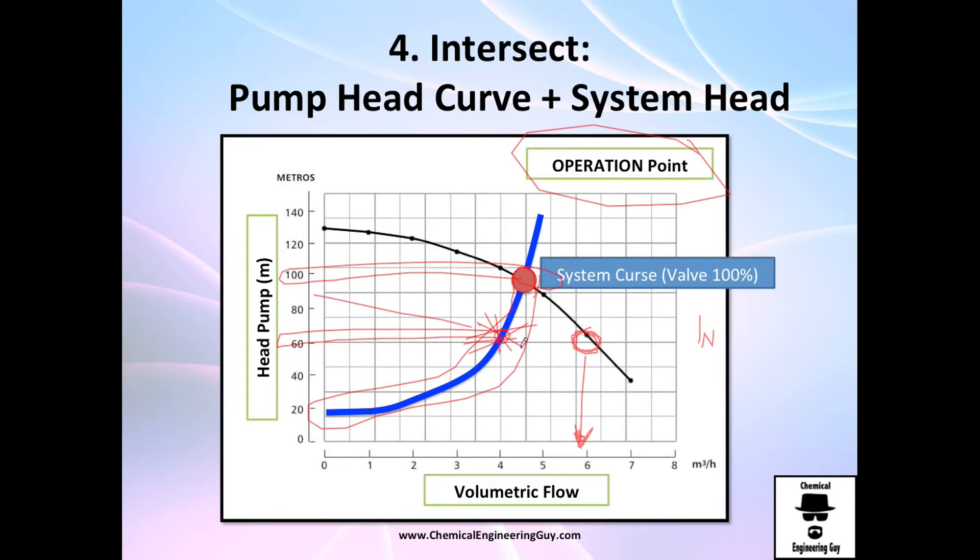The only thing you can do is find another pump that will deliver this point. So what I'm telling you is, if you want to operate this point right here, you need to install an impeller or go and get another pump.